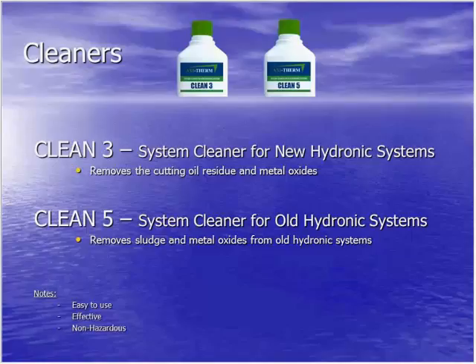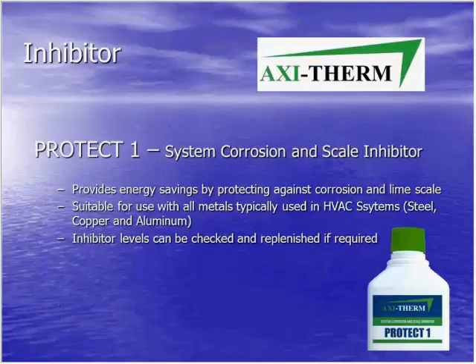We also have a system corrosion and scale inhibitor. It can help provide energy savings by protecting against corrosion and lime scale on heat exchangers, and it's suitable for all metals that are typically used in HVAC and hydronic systems. Inhibitor levels can be checked and replenished if required. Simply put a sample into a device with litmus test type paper and compare the colors, and if it's required, you just add a little bit more.